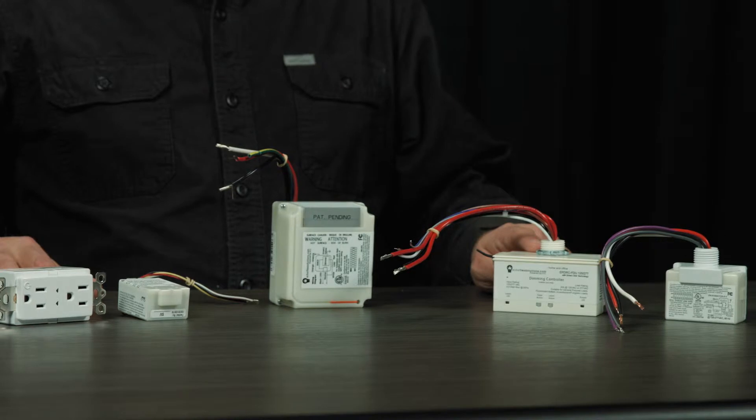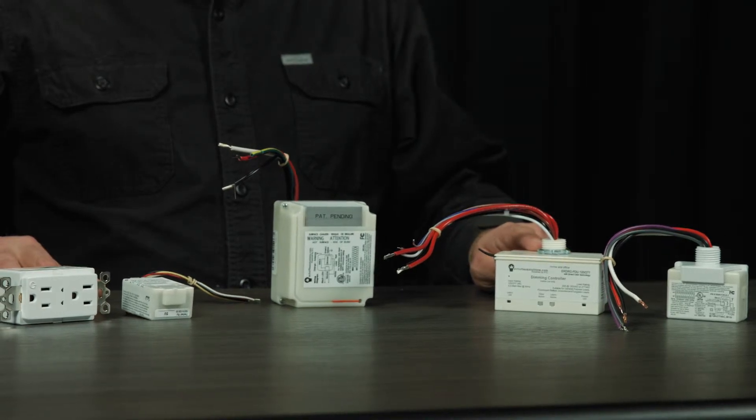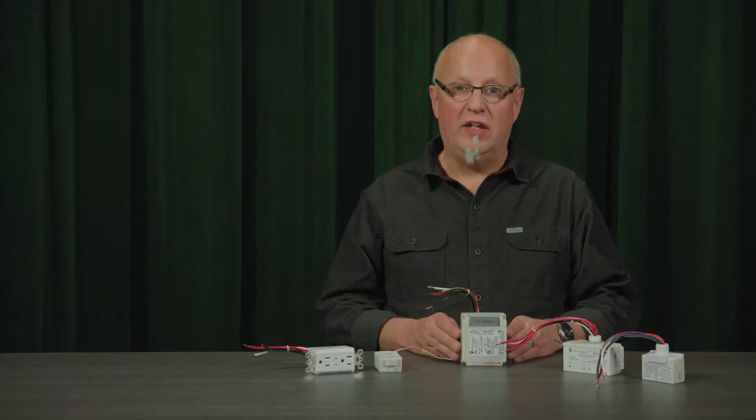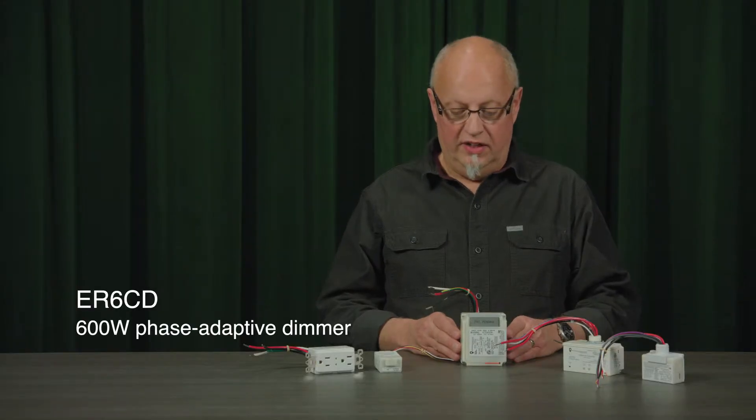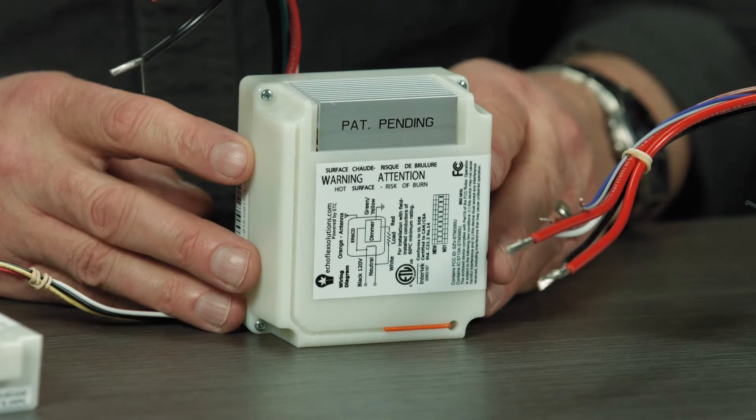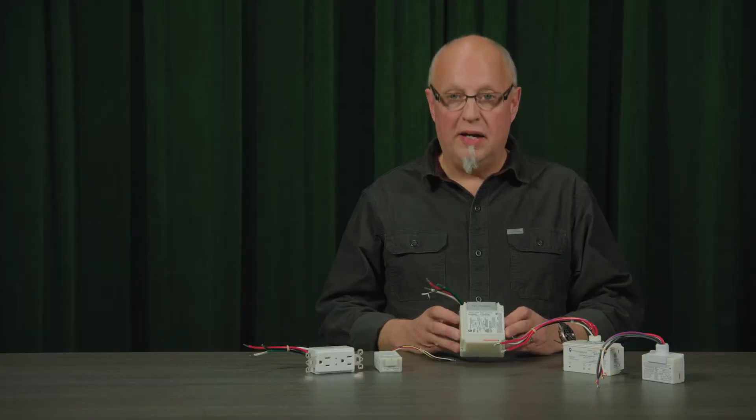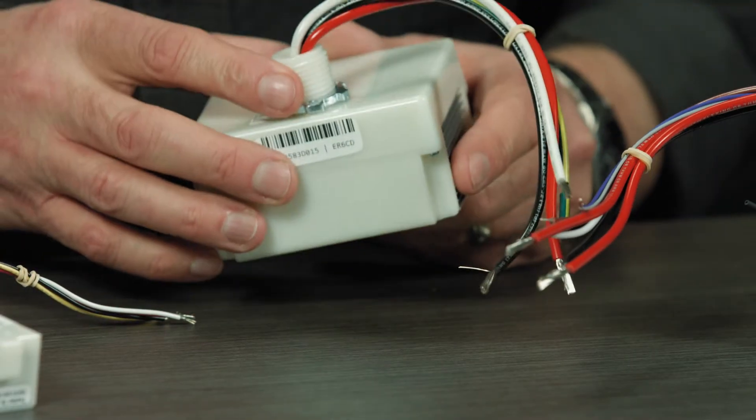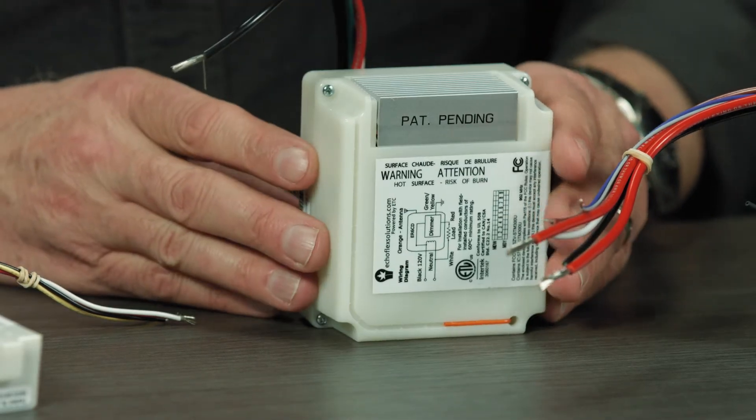The next one in line here is our phase dimmer, the ER6CD. It is a phase adaptive dimmer, which means that it can support reverse and forward phase dimming. It will support up to 600 watts of dimming. It is also a power pack style. All of these power packs are plenum rated. You can see the half inch nipple for mounting there on conduit.